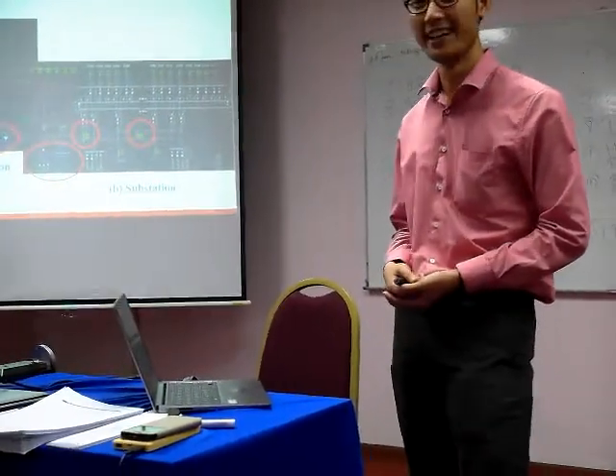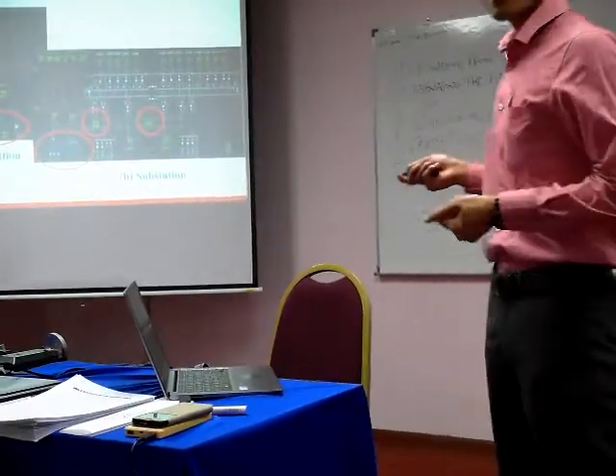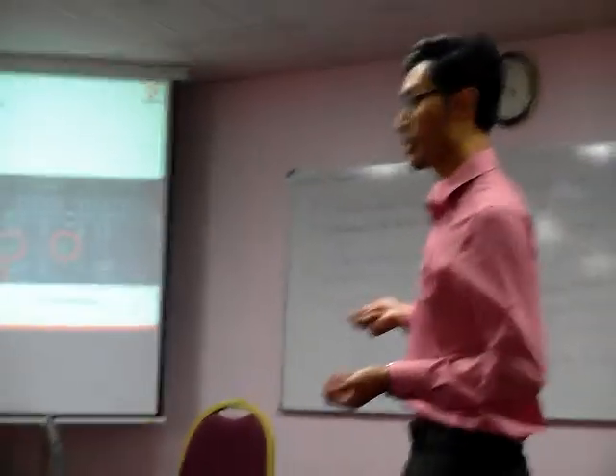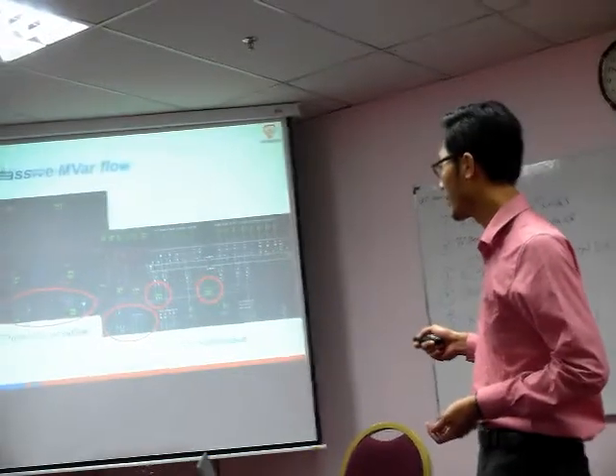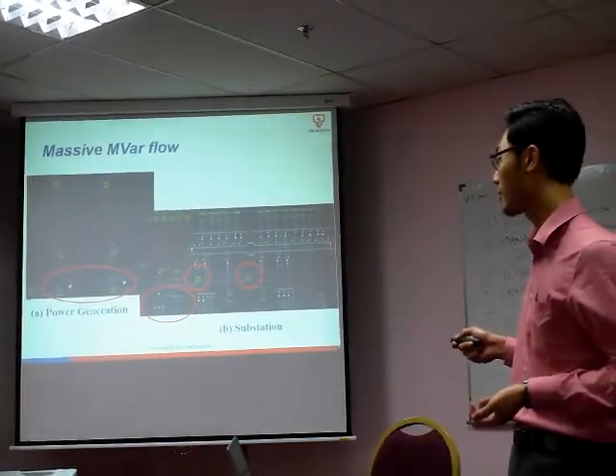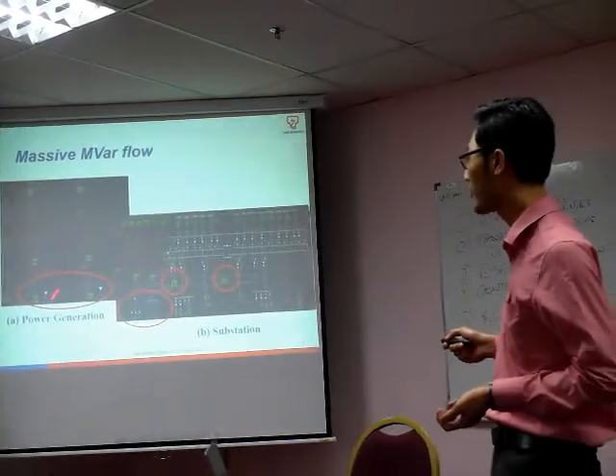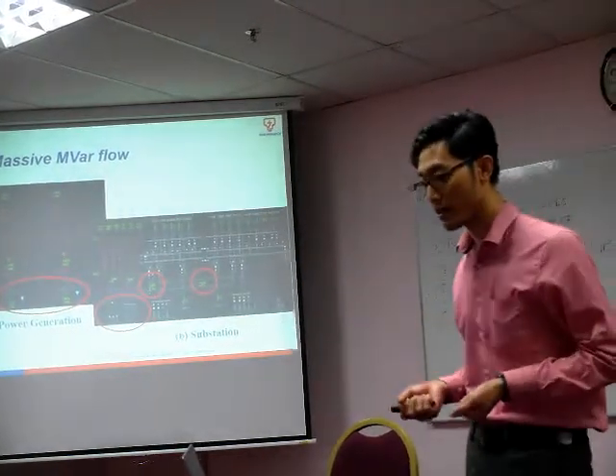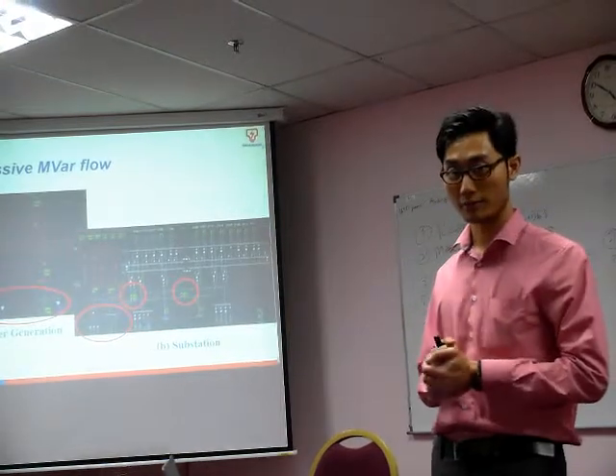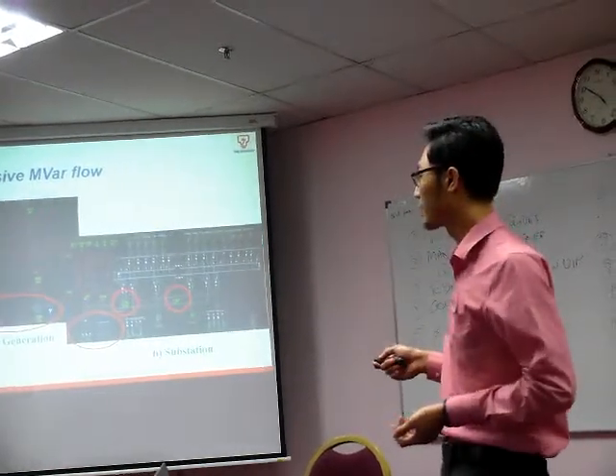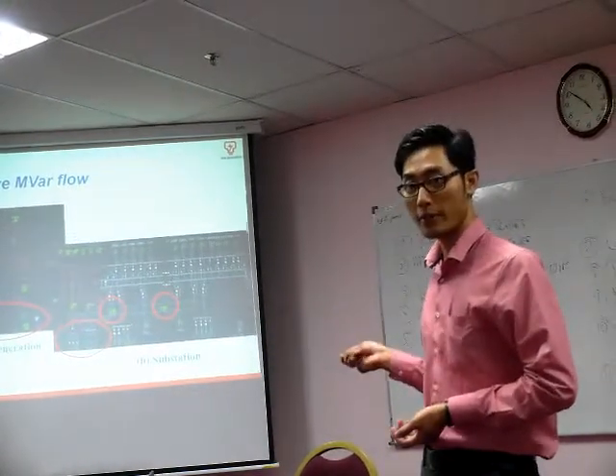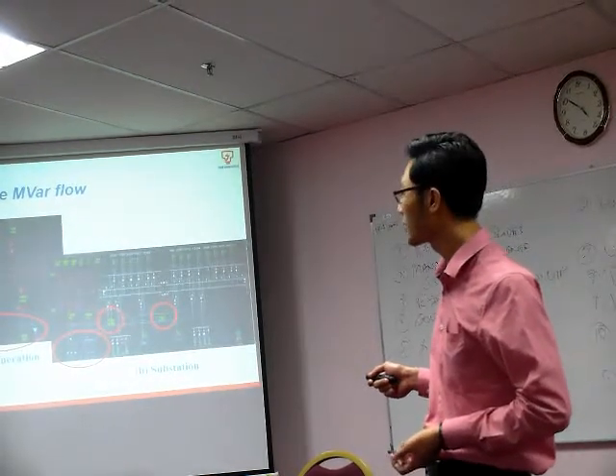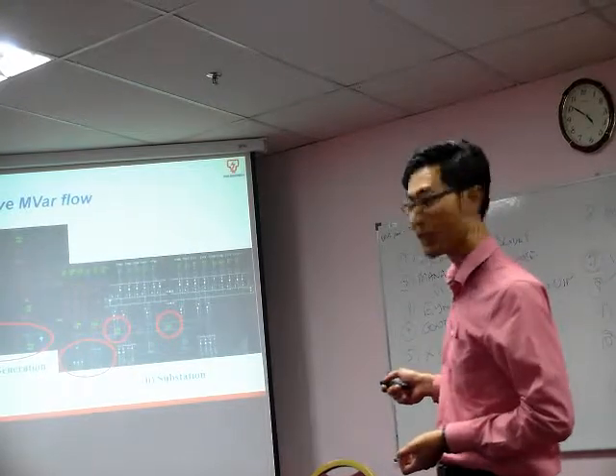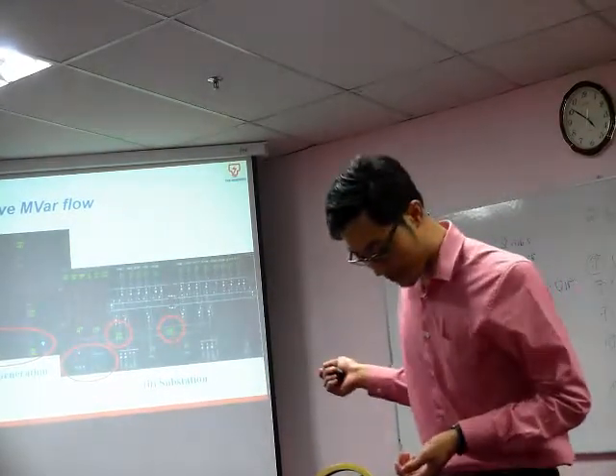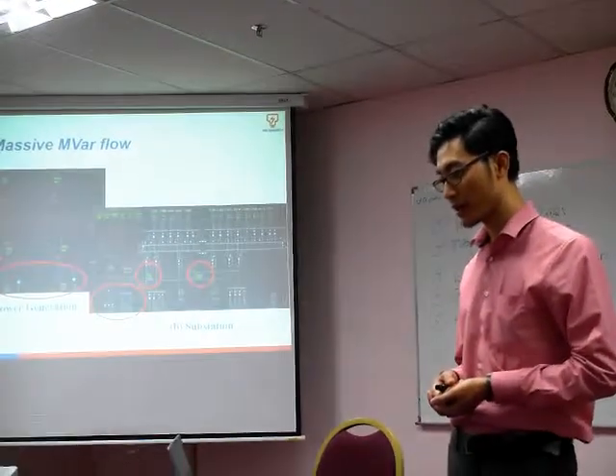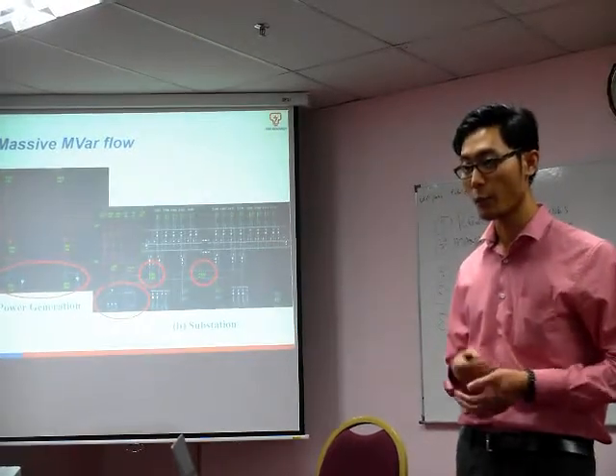But there must be a reason why you circled those numbers - what do you want to bring to our attention? This is a generator which can supply and absorb reactive power, and in this example they are supplying reactive power, and this is the reactor, where the reactor is absorbing reactive power. If the equipment supplies and this one absorbs, it shouldn't be this way - it should be this generator supplying reactive power to the load, not to this equipment, because the reactor should be used to reduce the voltage when the voltage is too high.